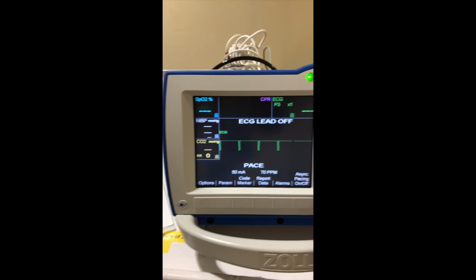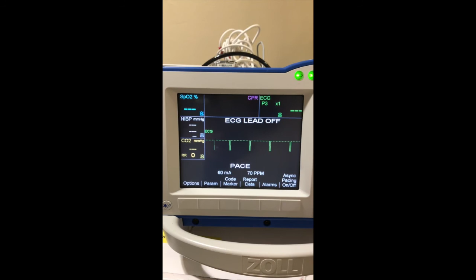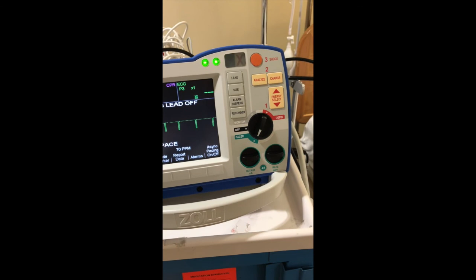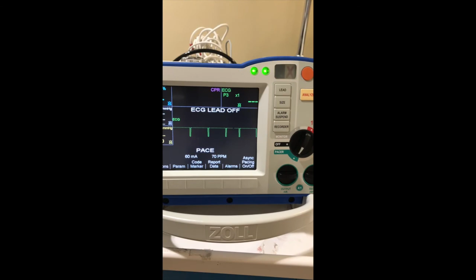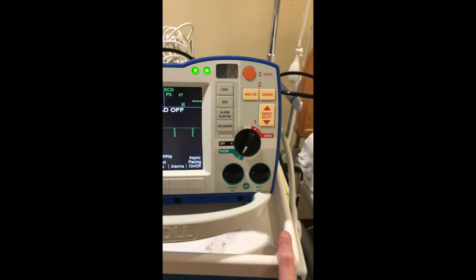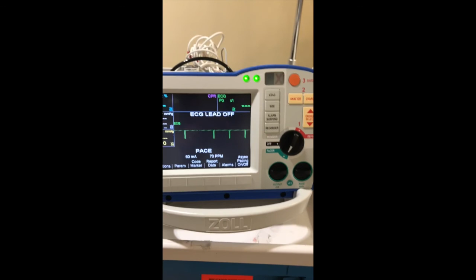So say you achieve capture at 50 milliamps, you want to go up another 5 to 10 milliamps above your threshold, and that is where you will keep your particular output. You're also going to have the rate set, which is usually determined by the doctor. Typically in a pacing situation, you'll have the rate set to 60 to 80, and 70 to 80 is most common in the emergency department.